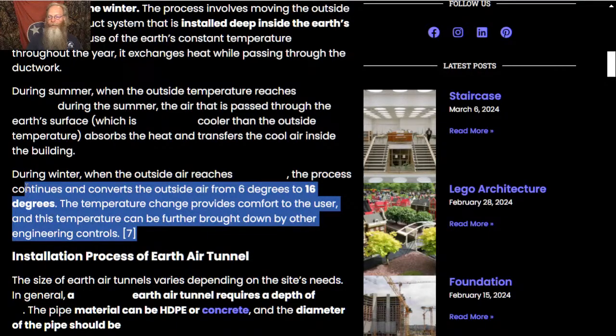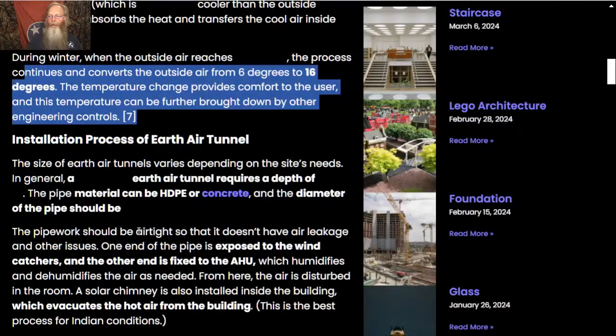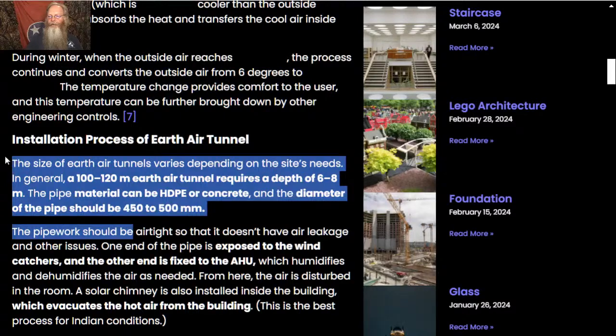Is that like a heat pump? The size of the earth tunnel varies depending on the site's needs. In general, a 100 to 120 meter earth tunnel requires a depth of 6 to 8 meters. The pipe material can be HDPE or concrete, with a diameter of 450 to 500 millimeters.